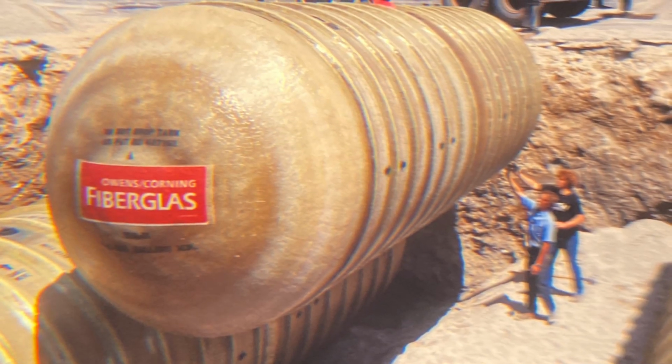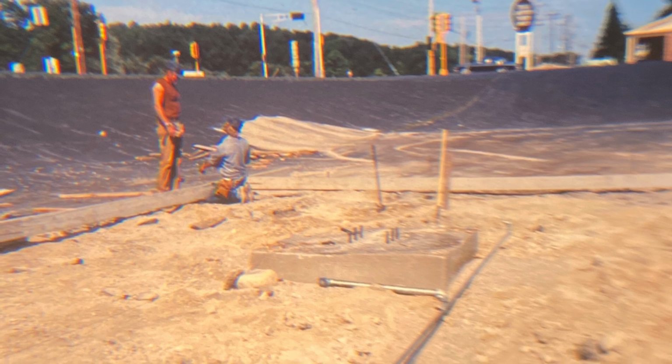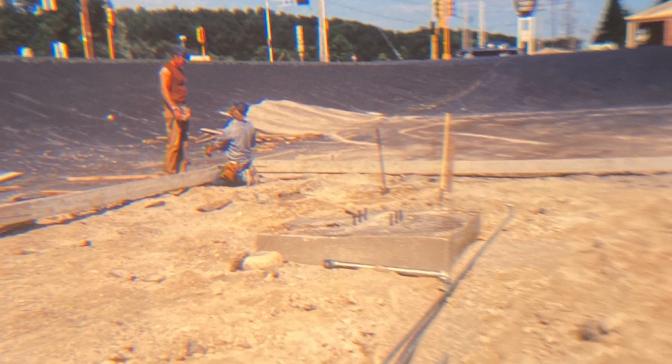So what they do is they clean up all the piping, they secure the tank before they do that, and then bring it up, and then they carefully remove them, set them on the side. Basically they crunch open, because these are fiberglass tanks. So they'll crunch open the side and cut open the side, basically. Go in, inert the material in there. They'll clean it out with Speedy Dry and absorbent and that kind of stuff. And they go and shovel that all out, and then they'll take the tanks and crush them up and throw them in a dumpster.